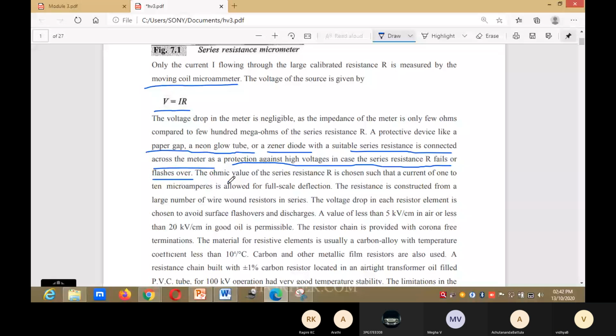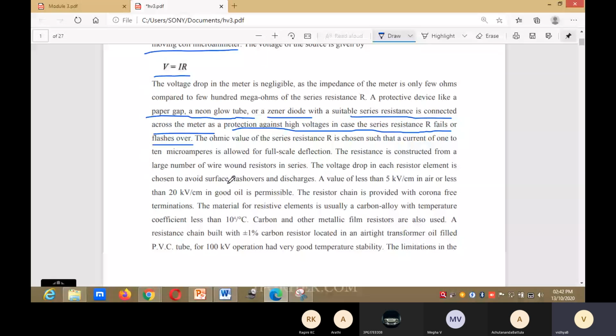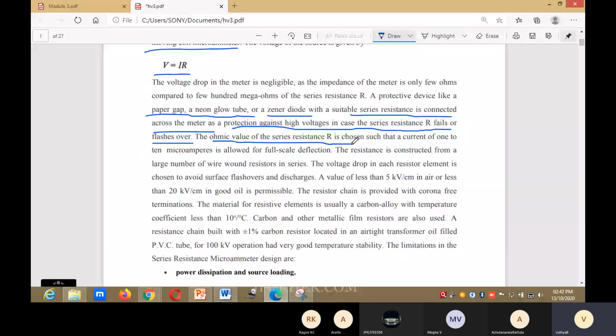The ohmic value of the series resistance R is chosen such that a current of 1 to 10 microamperes is allowed for full-scale deflection. The resistance is constructed from a large number of wire-wound resistors in series. The voltage drop in each resistor element is chosen to avoid surface flashover and discharge.